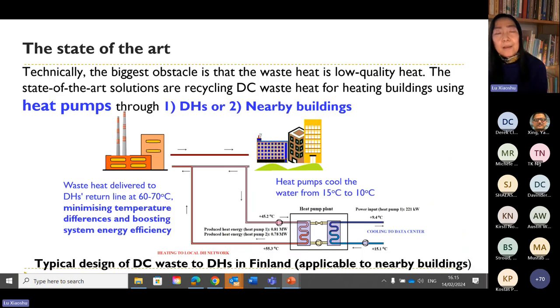Despite applications, this is a typical design of data center waste heat to district heating. It's also applicable to nearby building heatings. Here, you can see that the heat pumps are commonly used to cool the data center from 15 degrees to 10 degrees on one hand, and to heat the waste heat to supply to the return line on the other hand.